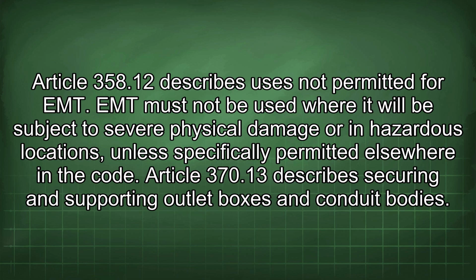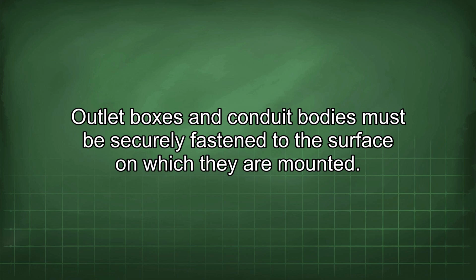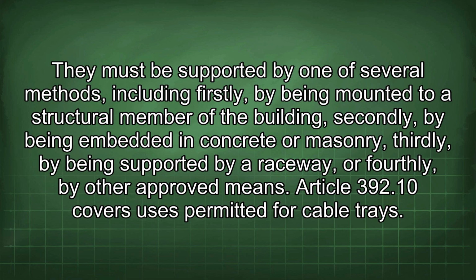Article 370.13 describes securing and supporting outlet boxes and conduit bodies. Outlet boxes and conduit bodies must be securely fastened to the surface on which they are mounted. They must be supported by one of several methods, including firstly by being mounted to a structural member of the building, secondly by being embedded in concrete or masonry, thirdly by being supported by a raceway, or fourthly by other approved means. Article 392.10 covers uses permitted for cable trays.